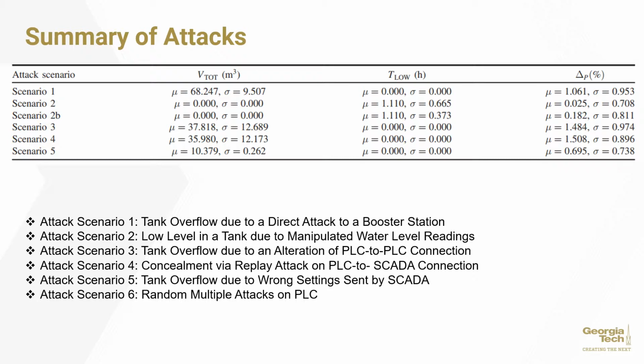For scenario number 1, we have a lot of total water, so a lot of overflow versus the normal condition. For scenarios number 2 and 2b, we have a lot less water compared to the normal condition that we should have. So these indicators basically present how much extra water we had, how many hours we had below the normal surface elevation of each tank, and how much extra energy consumption we had.